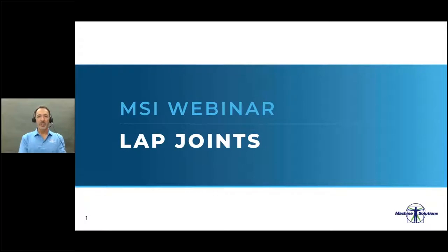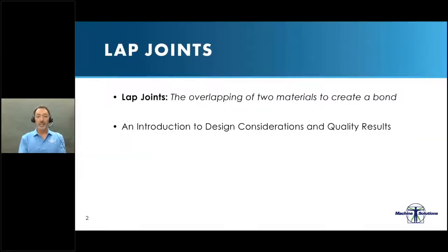Hi everyone and welcome to the Machine Solutions Tube Bonding webinar series. My name is Brian Beam and in this segment I'll be reviewing lap joints or overlap joints and everything you need to know to make great joints. A lap joint is where one material overlaps the other material for a certain length. The materials are then heated and an adherence is created between the materials. This is typical of balloons but it can also be a shaft to another shaft.